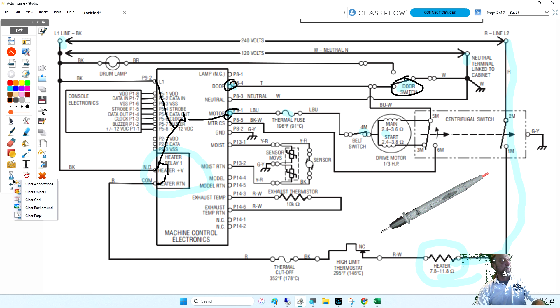So going back to the schematic, I don't have voltage here and here. What meter lead do I move, and where do I move it? There's two ways you could go. Someone give me one way to make another test. Or to neutral, motor to neutral. So I'm moving this P84 lead down here. Let's say I got 120 volts there. What's wrong?